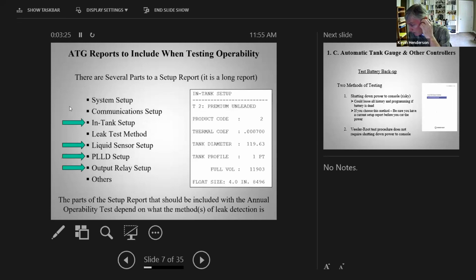And so typically what you think about when you're verifying the system configuration is you're looking at the setup report. This is what Veeder-Root calls it, the setup report. And so if you just walk to the Veeder-Root, hit the function key one time and go to the next mode, the setup mode, and hit print, then you'll get this very long report. And it can be really, really long depending on what modules are plugged into the system, of course. There's only certain parts of it that you need to archive, if you will, and make part of the annual operability test report. Generally speaking, you're always going to see the in-tank setup portion of that setup report.